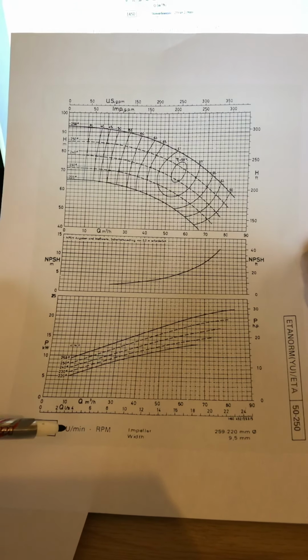Okay, so for argument's sake, let's say that we have a pump that pumps 30 cubic meters of water per hour with a 220 millimeter impeller. So what that means is you'll take this graph and say, okay, the 30 cubic meters per hour that the pump is pumping is going to be this line upwards. So this vertical line is at 30. Maybe if I hold it closer, you'll see that there is 30. And everything upwards from 30 on the horizontal axis is that flow rate. And then it says the impeller is 220 millimeters. So here you've got 220, 230, 240, 250, and 259. So those are the values that you will need.